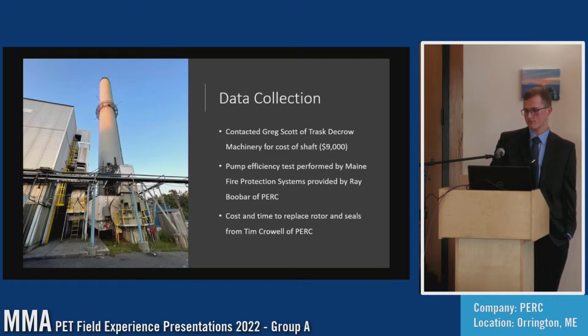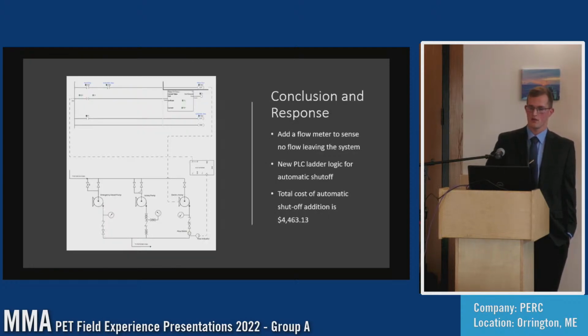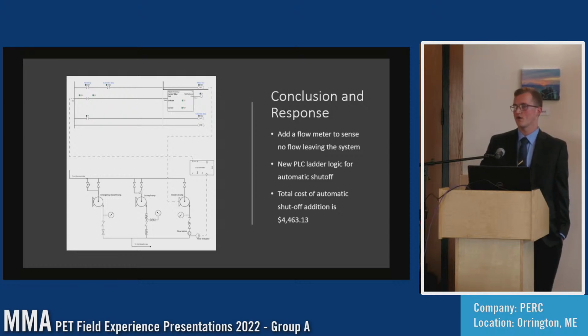All of these pretty much were a day. The shaft replacement would have taken a day. The seal could have taken a few hours. It all depended on who was on staff and who could work on that type of machinery. In conclusion, I discovered that the pump was operated off of a PLC system, and I used some basic ideas from our automation class from last year to rewrite the PLC programming and add a timer on delay, which activates a coil to open a contact and shut off the main power to the pump after a 15-minute timer.